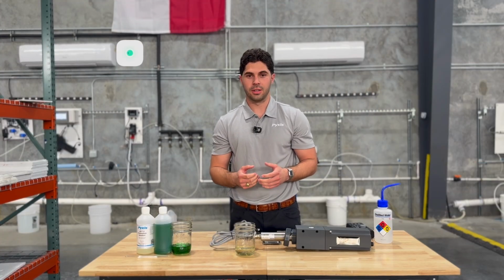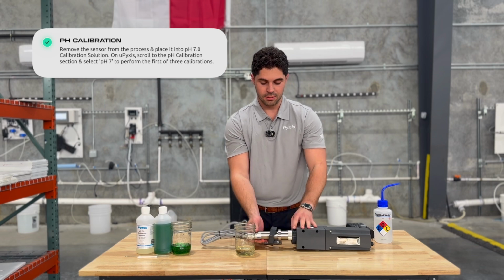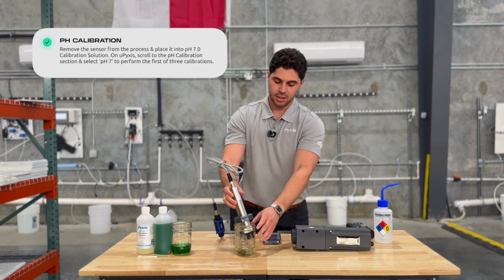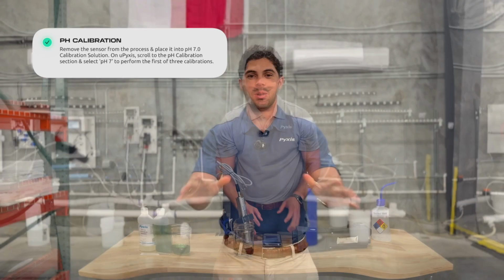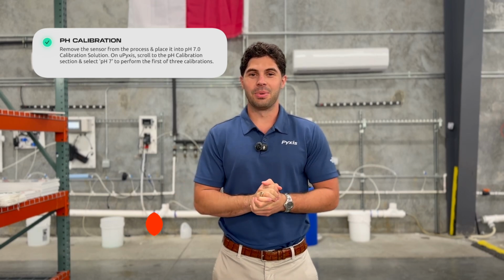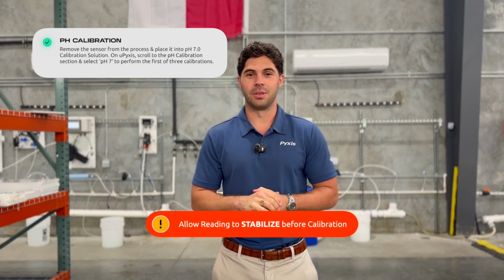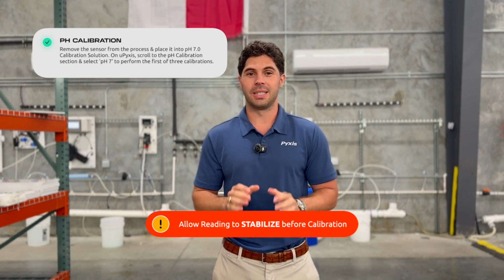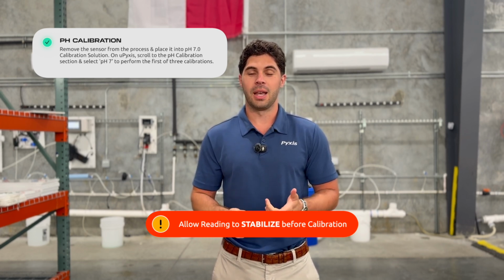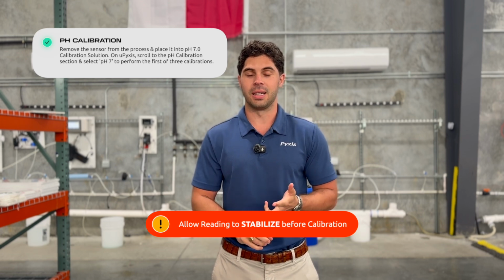For the pH calibration, you're going to remove the sensor from the process, place it in a pH 7 buffer solution. After placing your probe in the pH buffer solution, we want to emphasize how important it is to wait and let the reading in the app stabilize before hitting confirm in all of the 7, the 4, and the 10 solutions. That way we can be as dialed in as possible.